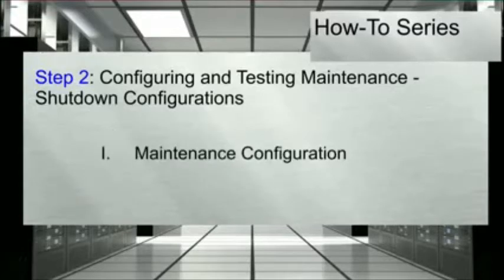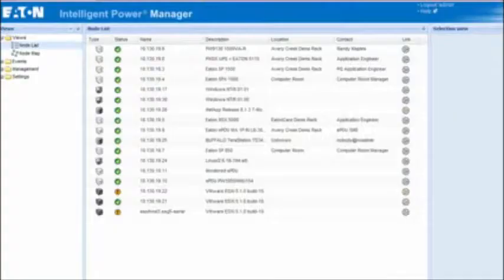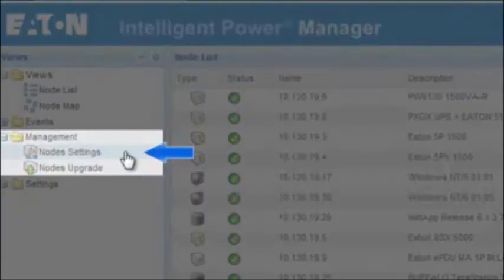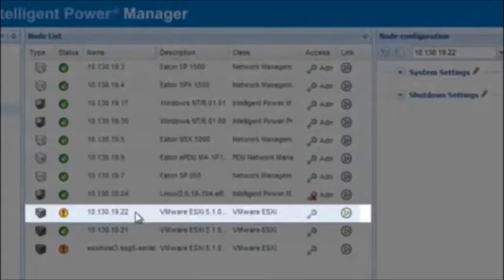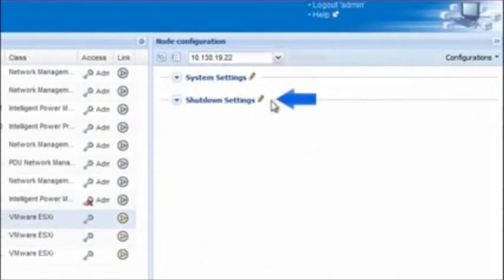We will begin by reviewing the maintenance configuration. Once the UPS supporting the selected ESXi host experiences a power event, IPM will trigger maintenance mode. As maintenance mode initiates, VMware's vMotion tool will migrate all of the virtual machines onto the other available ESXi hosts. In order to set the parameters, start from the IPM Views screen. Select the folder titled Management and click on the option for Node Settings. Choose the VMware ESXi host that you would like to configure. Once selected, the Node Configuration pane will open to the far right of the screen. By clicking the pencil icon, you will activate the ability to edit the parameters.